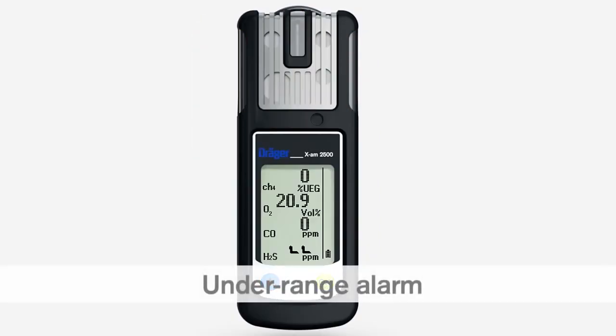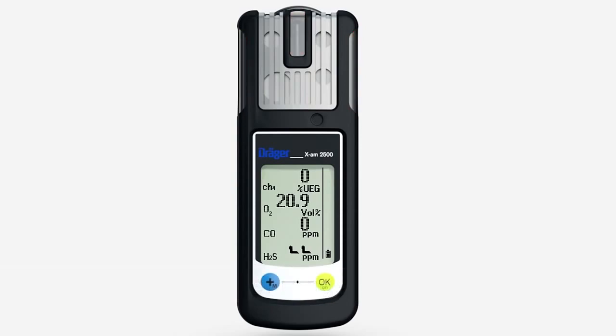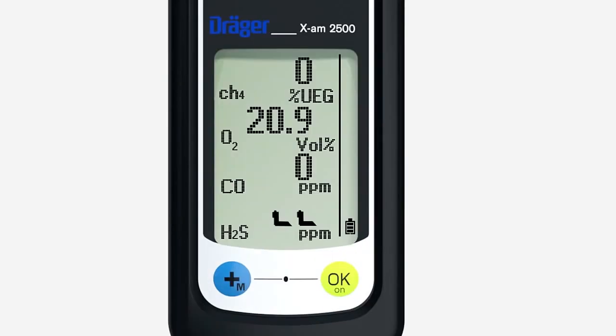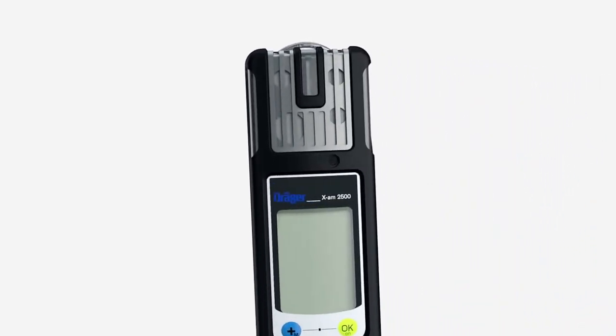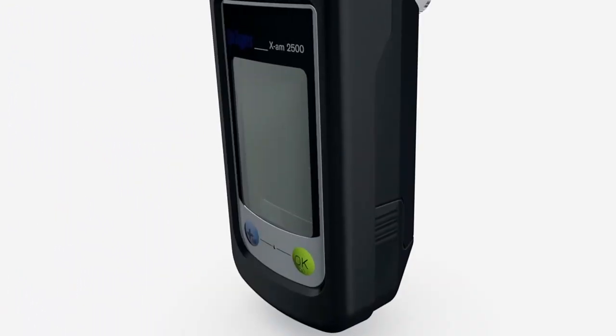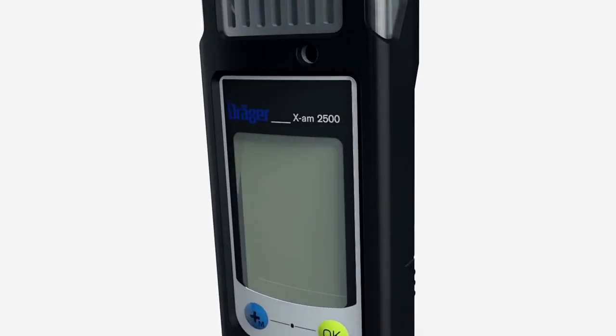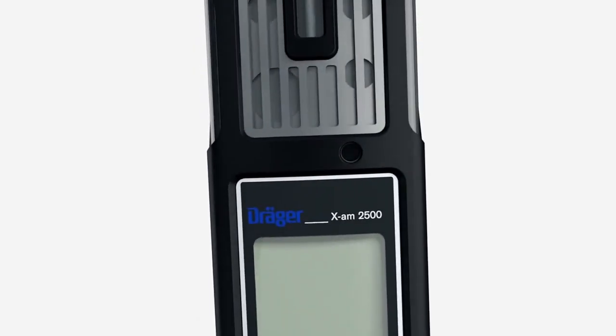In an underrange alarm, in which the measuring range is not reached, the audible, visual and vibration alarms are repeated. The underrange symbol is shown in the respective measuring field. This indicates that the measured value is negative. This can occur if, for example, a fresh air calibration has been carried out in an area where concentrations were already present. Perform fresh air calibration immediately in an area of fresh air. This alarm cannot be acknowledged.